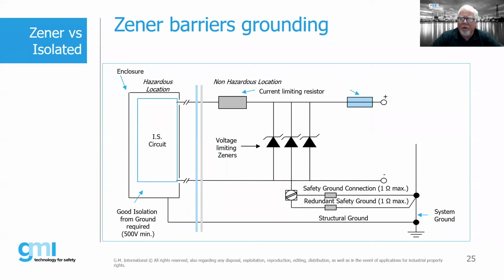So a lot of people, which is good engineering practice, use two redundant, if you will, safety ground connection points for your intrinsically safe circuits. It's not mandated unless it's a client-specific specification. The standards don't require it. For the most part, I have yet to see a standard that says that you must use it, but it is a good engineering practice, and there are some stipulations that are spelled out in various world regulations.